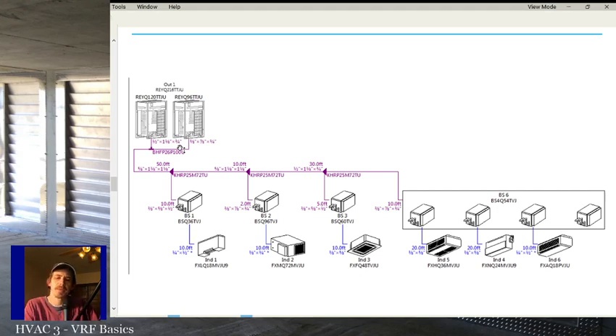You need to keep the velocity high enough that you're returning oil to the outdoor unit, returning oil to the compressor efficiently. And some of them actually go through special cycles where it just works to return oil to the outdoor unit, because when you've got all that line set and a lot of lines running to different places and a lot of indoor units where the suction pressures are going to vary a little bit from unit to unit as it returns to the system, you're going to lose oil.